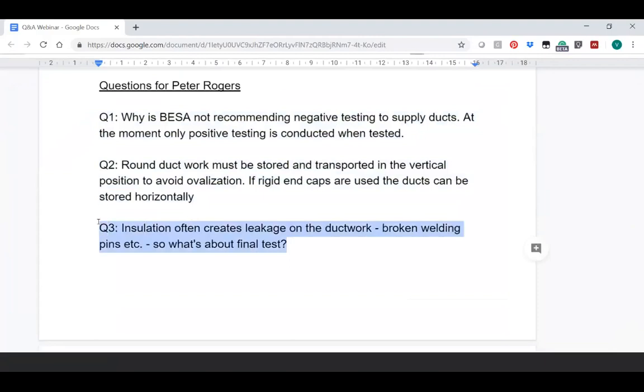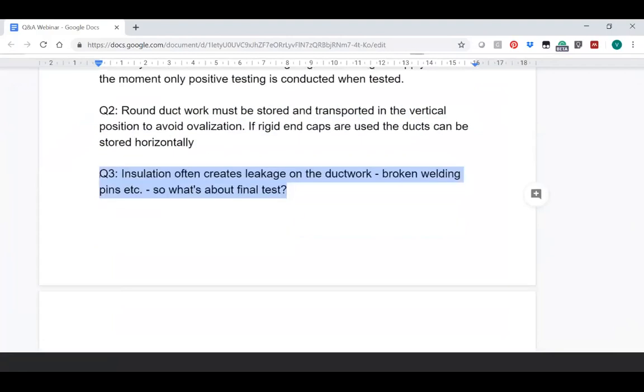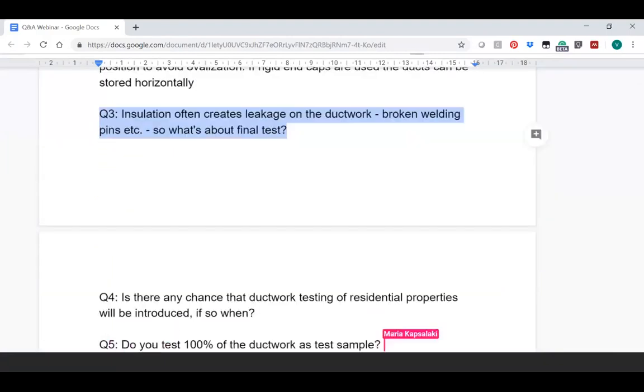Okay, and insulation often creates leakage on ductwork - broken welding pins, etc. So what about the final test? Well, the main thing is to test initially before the insulation is put on, so that you know the test has passed. Then you can do a final test after the insulation, and of course, if it should fail at that particular point, it means that whoever installed the insulation has obviously pierced the ductwork. So yes, a final test should obviously read the same as the initial test, and certainly can be done.